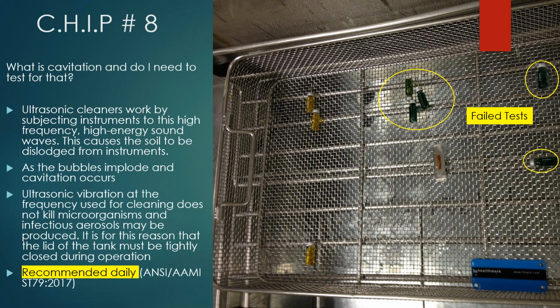So what is cavitation? Ultrasonic cleaners work by subjecting instruments to high frequency, high energy sound waves, and that causes the soil to dislodge. There are little implosions that happen, and that actually pulls soil away from the instrument, as those air bubbles implode and the cavitation occurs. Ultrasonic vibration at the frequency used for cleaning doesn't kill microorganisms, and infectious aerosols may be produced. So that is the reason that the lid should stay closed. In many automated machines, the lid closes automatically. So that is another little bit of a caveat. It's hard to tell what is going on inside these machines when the lids are always closed.